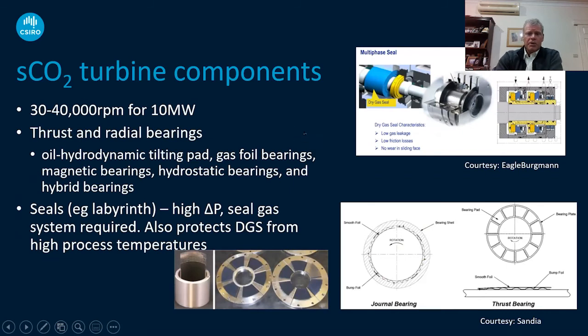The other critical turbine components that Jeremy mentioned are the bearings and seals. For small turbines around 10 megawatts, we've got 30 to 40,000 RPM, so very high duty cycles happening, and getting bearings that operate at those speeds is not conventional stuff.